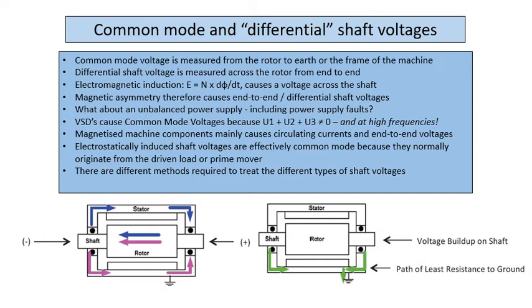The reason it's not so much of an issue in power frequency is because your capacitive impedance between your stator and rotor is much higher for 50 hertz than it is for the 100 kilohertz and above that Stian's presentation was about.